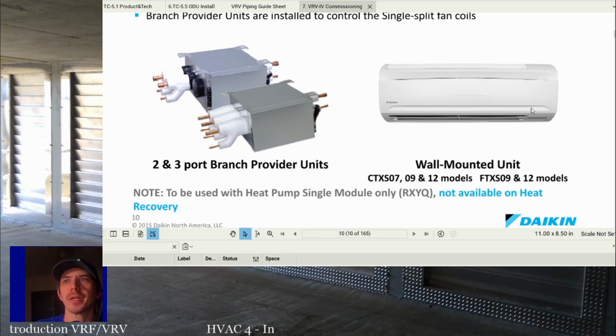If this is running in heating, it'll say, okay, I need high pressure gas to the unit, and then liquid's going to come back. And the only application where you do not need a branch selector box for a unit or set of units, and we'll see what that looks like when we look at piping, is when that unit is cooling only. Because remember, we always have a liquid line and we always have a suction line. So if we connect this unit to two pipes off the heat recovery, if we just connect it to liquid and suction, it will always be an AC only unit.